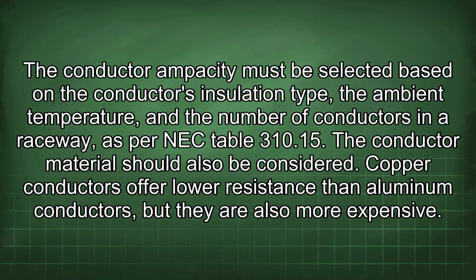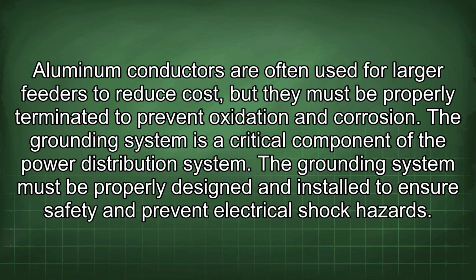The conductor material should also be considered. Copper conductors offer a lower resistance than aluminum conductors, but they are also more expensive. Aluminum conductors are often used for larger feeders to reduce cost, but they must be properly terminated to prevent oxidation and corrosion. The grounding system is a critical component of the power distribution system.